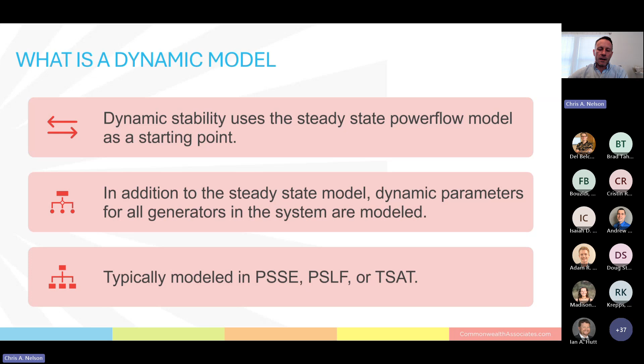So to create a model, some of the information you need, just for a single generator site, for example a single conventional generator—might be large or small—you'll need the cable schedule for all the cabling from the generator to the point of interconnection. You need transformer specifications, and the more detail you have, the better. We can usually make estimations, but if you have the actual transformer test report, the better data you have, the better output you'll get.